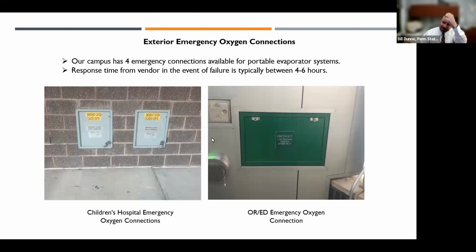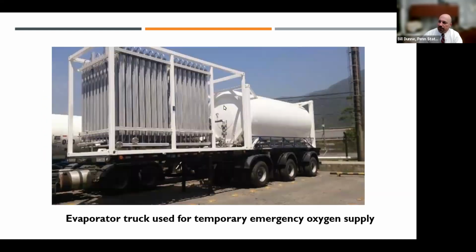We also have redundancy that allows us to bring in temporary evaporators, with emergency connections. So if the tank farms failed, or we had simultaneous emergencies, or couldn't get those feeds in for whatever reason, we have backup areas where we can bring in a vendor with liquid oxygen and a portable evaporation system. When we need to supplement our oxygen supply, like we had to during COVID, this was a strategy used at many hospitals to increase the volume of oxygen available in the system. This is what that looks like.